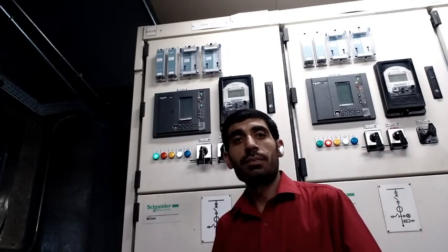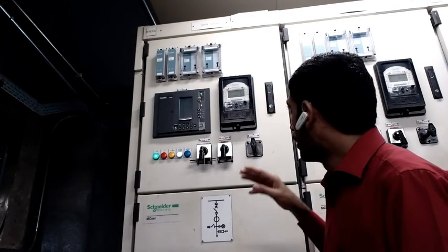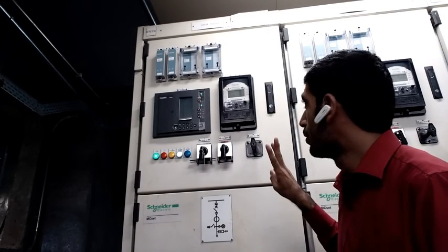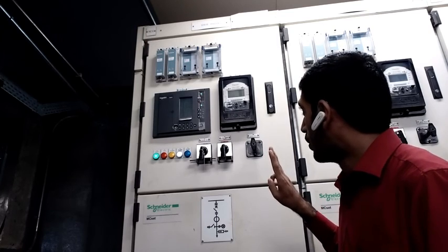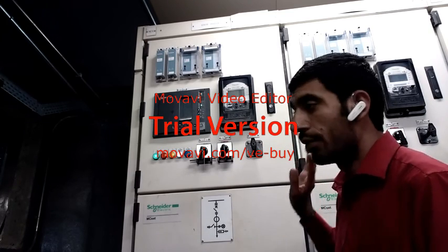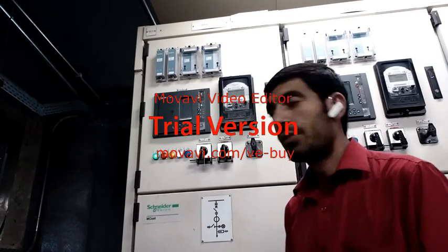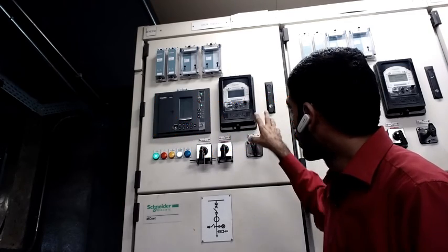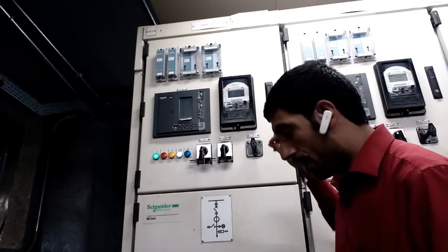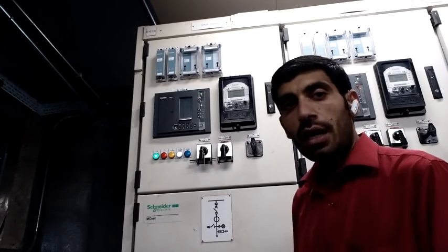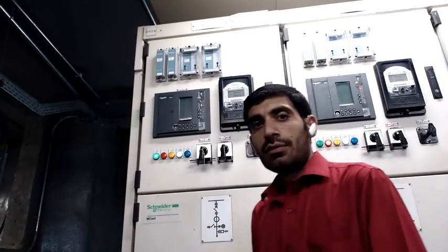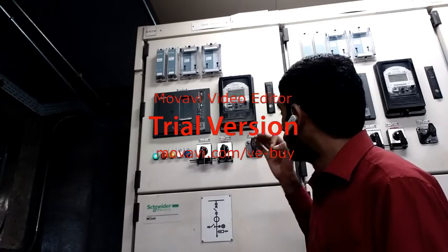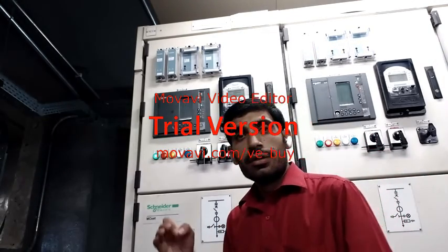This multifunction meter we also test through Freja, through CPC. We inject 3-phase voltage through Freja and 3-phase current through Freja. We inject here and check the values. We inject actual values, 0.25, 0.5, 0.1 through Freja, and check the values on this multifunction meter, how much error it gives, and we check the error between actual values and the rated values. And we also inject the same thing.